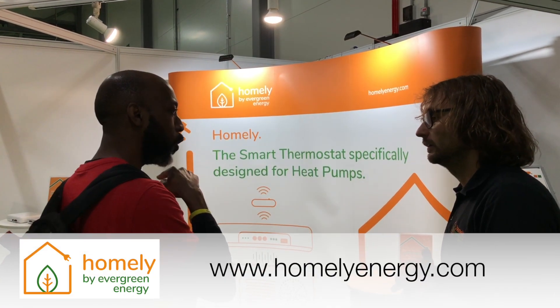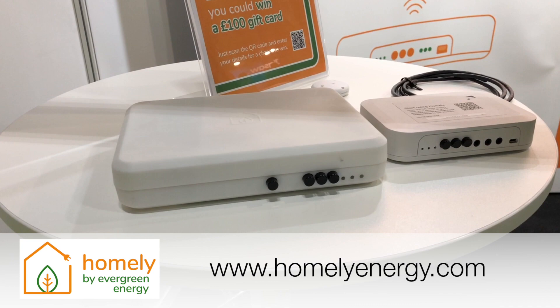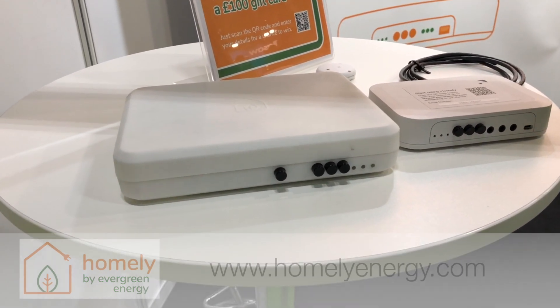While looking around the stands, we noticed Homely — a start-up with a product designed to make using a heat pump even more efficient. The theory goes that if you control your heat pump like it was a gas boiler, turning it on when you need heat and off during the day, you won't achieve the full efficiency of the heat pump. But by leaving it on during that time at a lower setback temperature, the heat pump can maintain its efficiency, and even though you may lose heat during those in-between hours, overall, because of that increased efficiency, you will have used less energy. It sounds counter-intuitive and is a very different way of thinking compared to what we're used to for traditional heating systems.